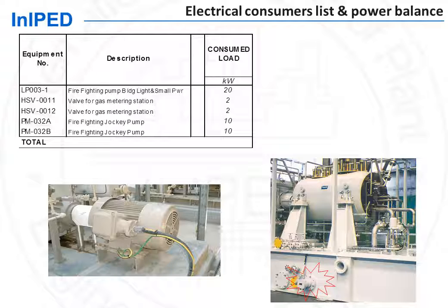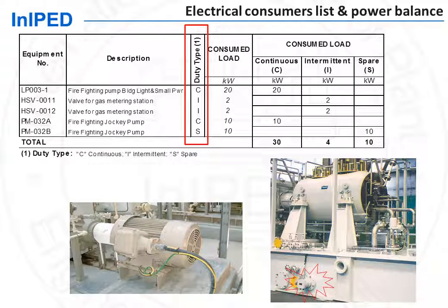Not all consumers operate at the same time. Therefore, to estimate the overall plant power consumption, one must take into account the type of operation, whether it is continuous or intermittent. This is done by identifying in the electrical consumers list the type of duty: is it continuous, intermittent, or spare? A spare equipment, for instance, operates only when another one is not operating.